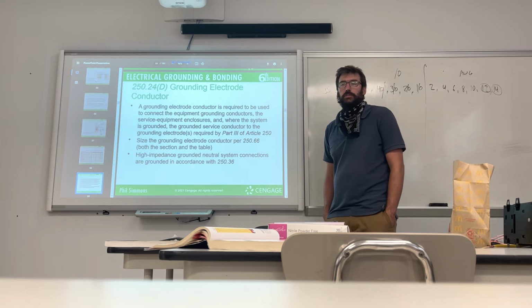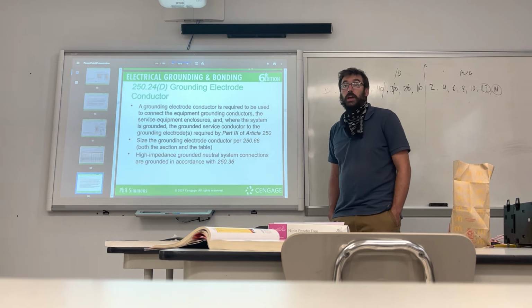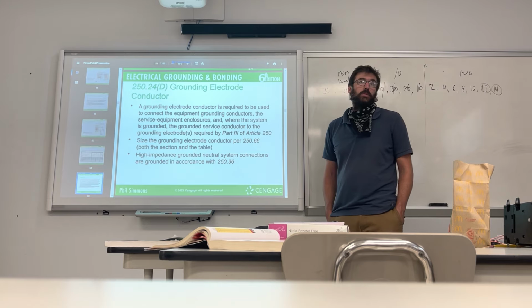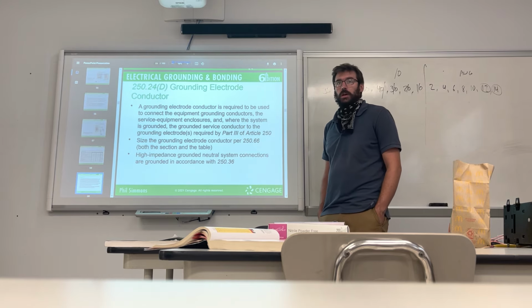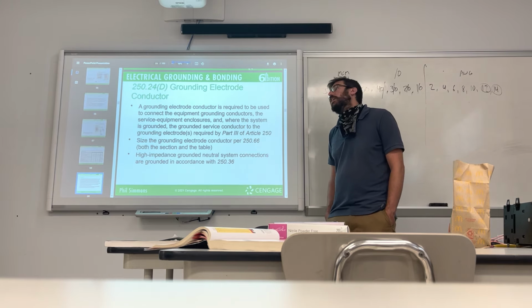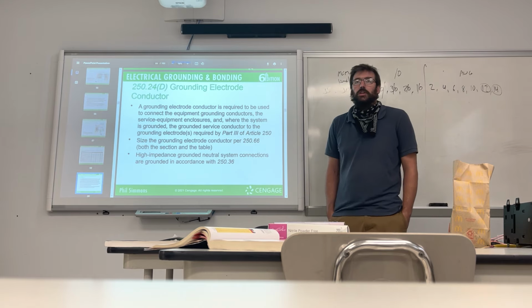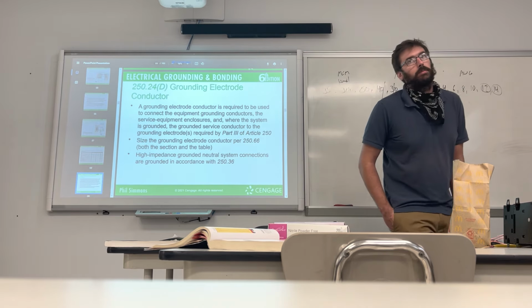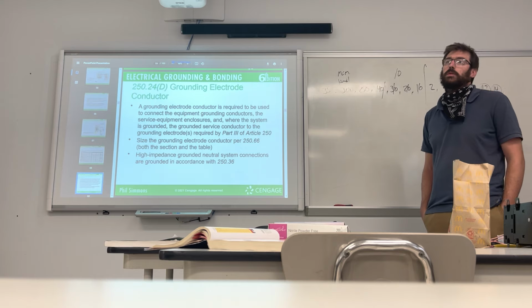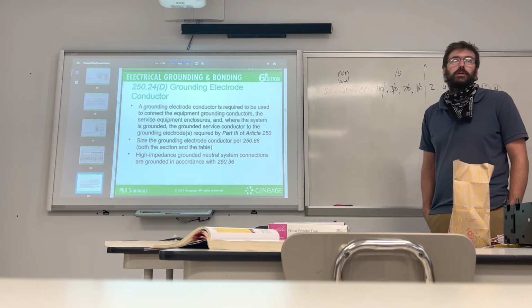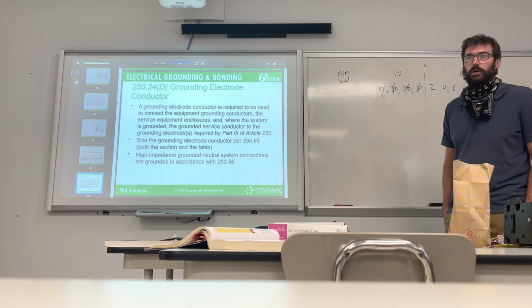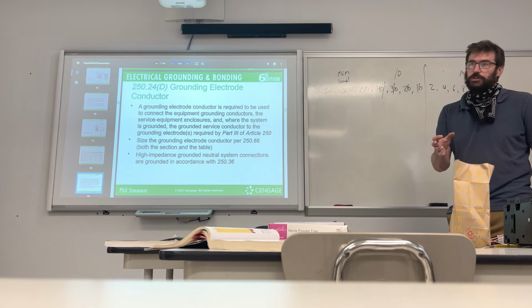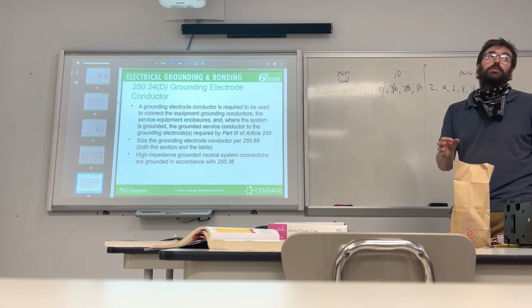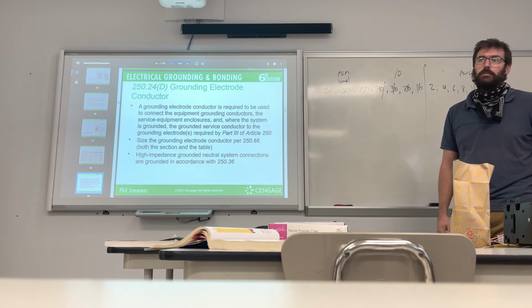You know what I mean? If you're grounding a 1,000 amp service, it's going to look a lot different than the puny little one we have in residential systems. Now the reason that one is 5/8, it's going to handle everything up to 200 amps. But beyond that, you might need a special ground rod or grounding electrode to fit the bill of what you're dealing with. So there's probably going to be a change in length, but most importantly, in diameter.